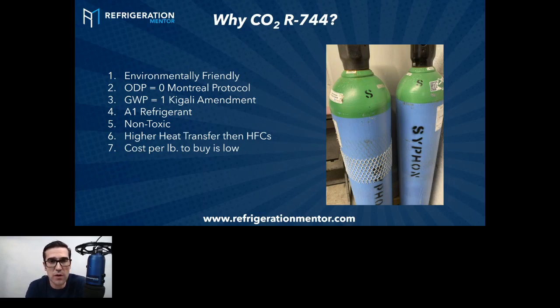CO2 is an A1 refrigerant. Depending on the application you work on, you're going to hear about A1s, A2Ls, and A3s. A2Ls are mildly flammable refrigerants, kind of like R32, which is actually a component in 410A, but now classified as mildly flammable. There are different rules and regulations for a refrigerant like that. Then you have A3s, like R290 or propane, which are flammable refrigerants. CO2, on the other hand, is non-flammable and non-toxic.